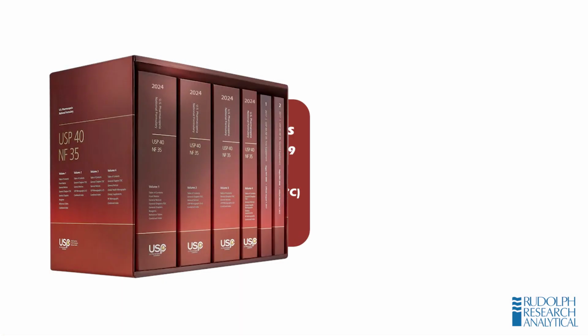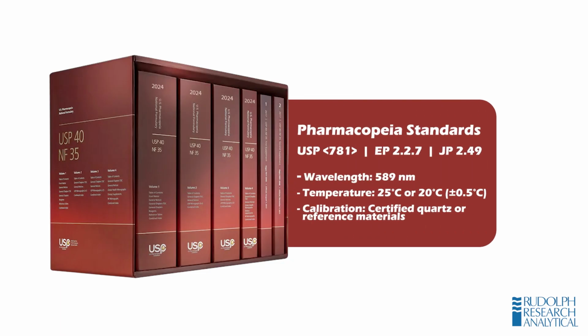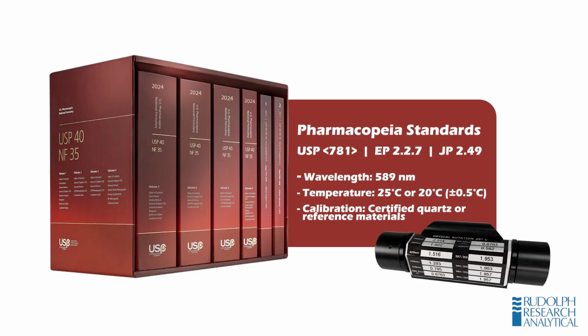Pharmacopeal standards define the framework for optical and specific rotation measurements. USP 781, EP 2.2.7, and JP 2.49 each specify conditions that laboratories must follow. These include the wavelength of light, typically 589 nanometers, the temperature, 25 degrees or 20 degrees Celsius within half a degree, and the calibration of the instrument using certified quartz control plates or reference materials. These standards make sure every measurement is accurate, traceable, and reproducible from lab to lab.